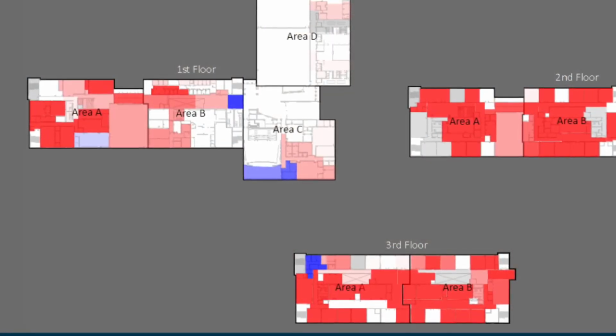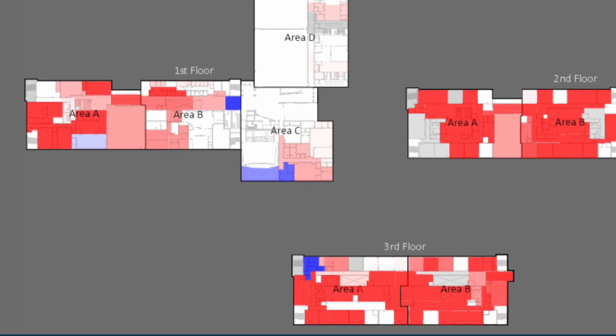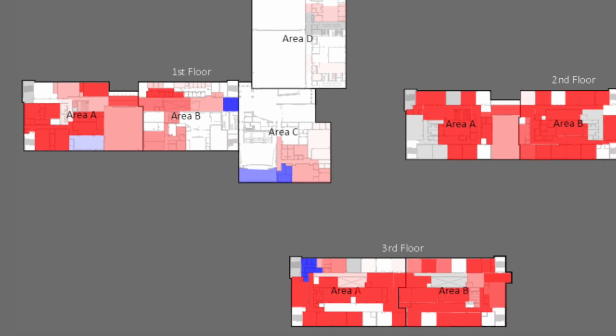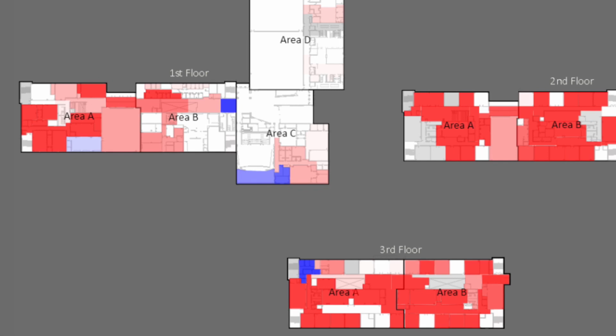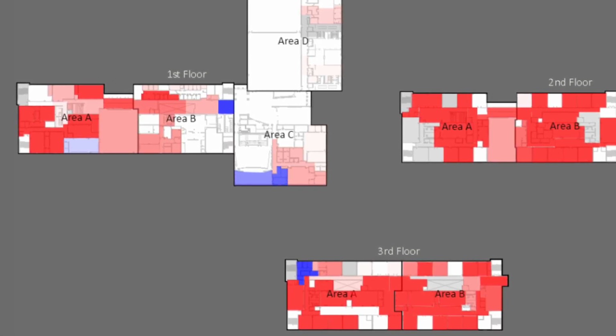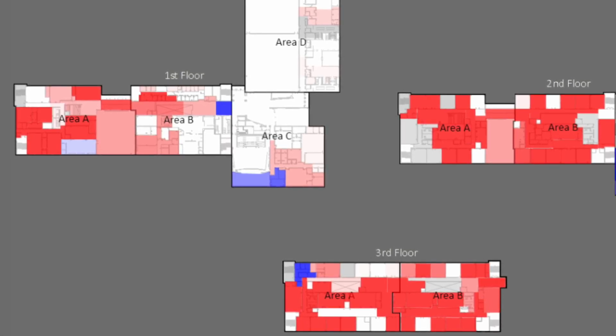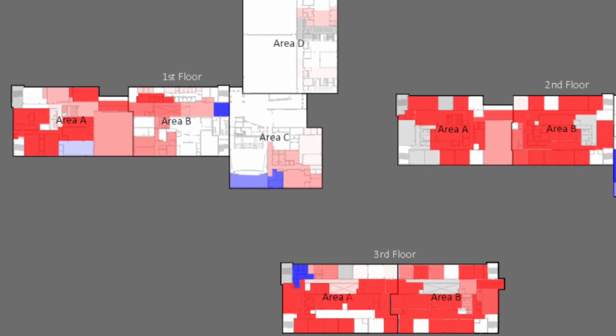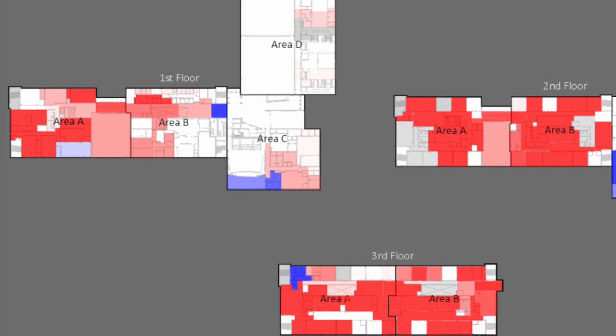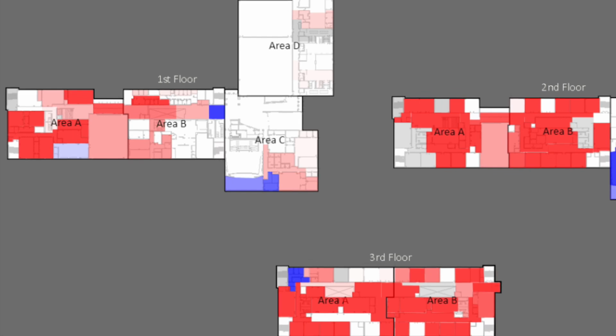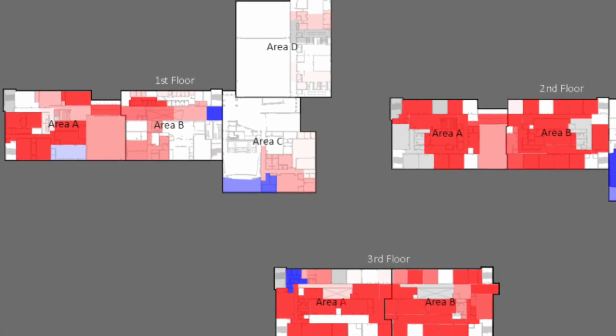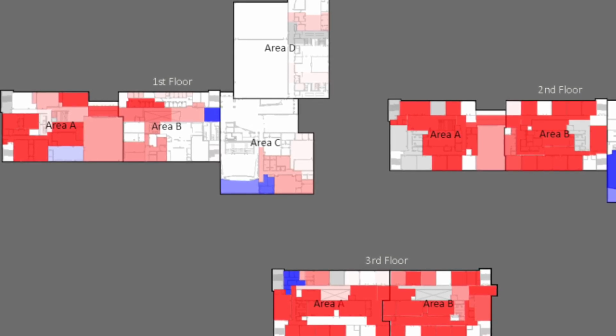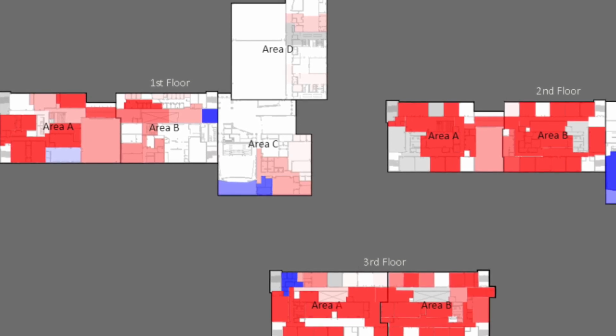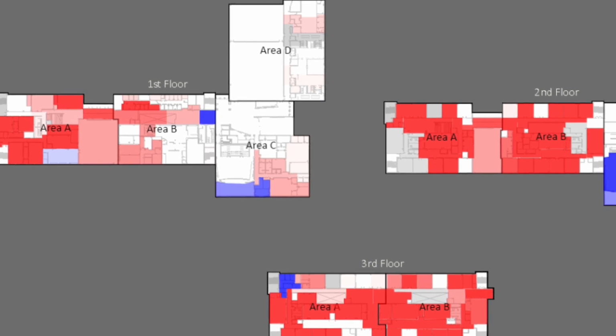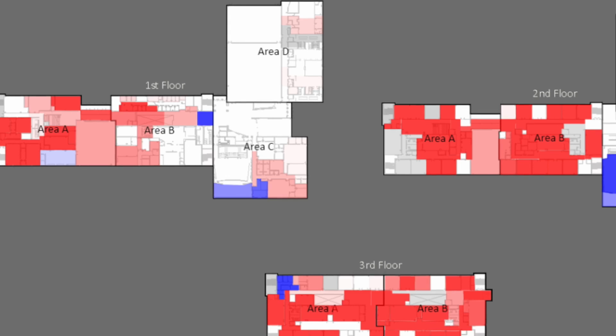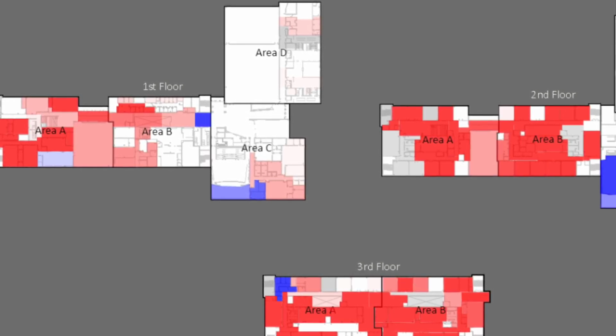All right, so this video is not going to be about the refrigerant cycle. This video is going to be about how you cool a building with a cooling tower. So we're gonna talk about the water cycle on the condenser side and on the cooling side, and how the chiller and the cooling tower operate together. All right, so what you are seeing right now is the same building where those cooling towers and that centrifugal chiller sit. They told me that the school was hot, so I didn't have any issues on my chillers or cooling towers. It was just a signal problem that I had. So what we're gonna do here is cool those rooms. And in this video, I'm gonna show you how a cooling tower and a centrifugal chiller do it. I'm gonna try to explain it the best I can, step by step, so you can have a good understanding of how it works.